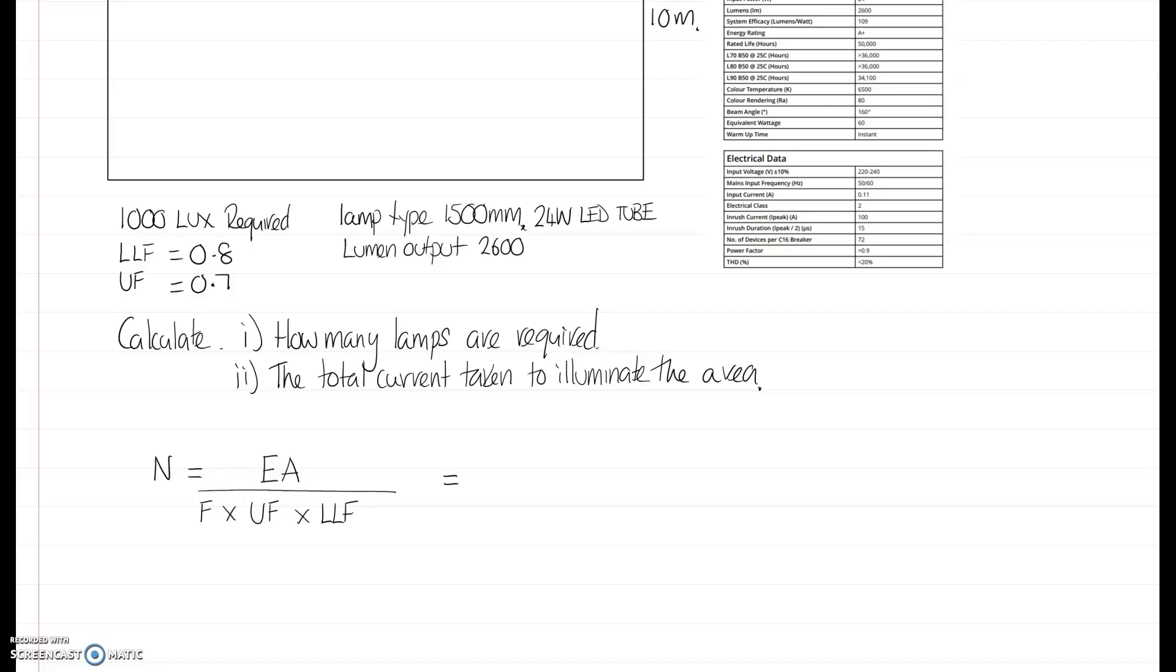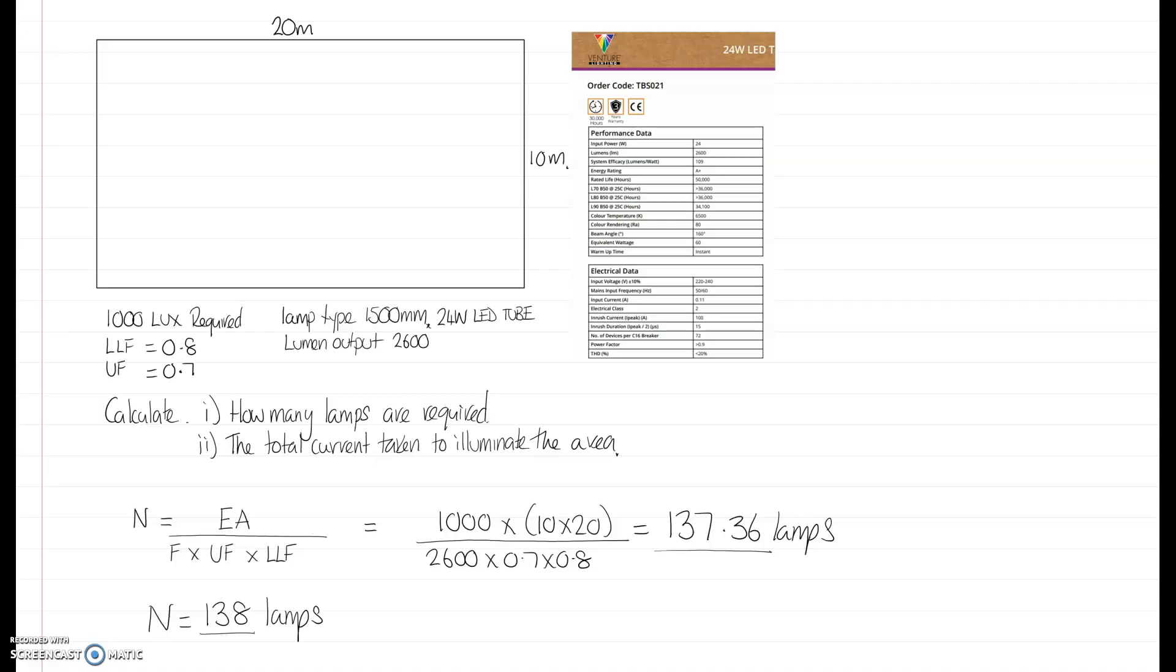We've got our formula. The illuminance required is 1,000, the area is 10 metres by 20 metres, and the lumen output per light is 2,600. The utilisation factor is 0.7, and the light loss factor is 0.8. So the total number of lights, we do the maths. That's 137.36 lamps, or 138 lamps. So what that means is we would need to divide this floor area. We would space out that floor area to put multiple rows of lights.